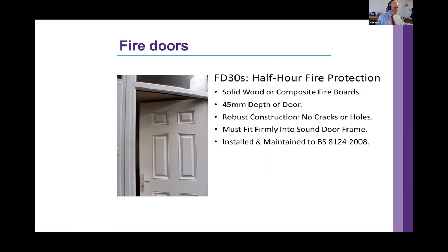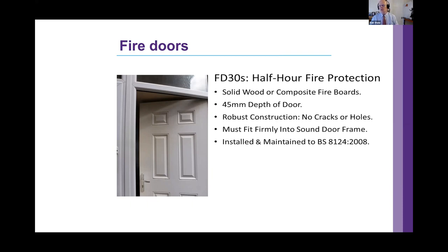Here we've got one you see in residential areas in high-rise blocks. This one doesn't have a letterbox, but if it did, the letterbox needs to conform to the same fire specifications as the door — it makes no sense if it doesn't. You can get fire-protected letterboxes that offer 30 or 60 minutes protection, depending on the door. The door is solid wood or more often composite fire boards. The FD60 door is 54 millimetres deep. The FD30 is 45 millimetres. The way I remember it: 54 is 60 minutes, 45 is 30 minutes. Certificated softwood or hardwood frames.